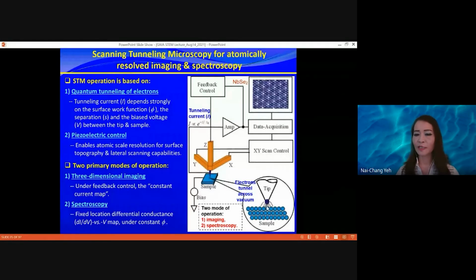The amount of electrons that can tunnel - the tunneling current - is very sensitive to how far apart your tip is from the sample. So if you fix the tunneling current using a feedback electrical design, the position of the tip will follow the surface modulation of these atoms. That's how you can do imaging - this is when you get topography, three-dimensional topography. You scan your tip along the XY direction, and you get modulations along the Z direction. It's a three-dimensional process.